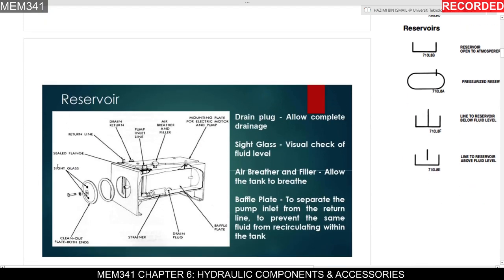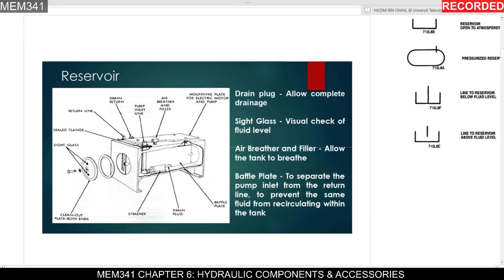The diagram of the reservoir is shown in this figure. It has a drain plug to allow you to completely drain the oil in the reservoir or tank container, a sight glass which is transparent to visually check if the fluid level is enough for the system, an air breather and filler to allow the tank to breathe, and a baffle plate to separate the pump inlet from the return line to prevent the same fluid from recirculating within the tank.